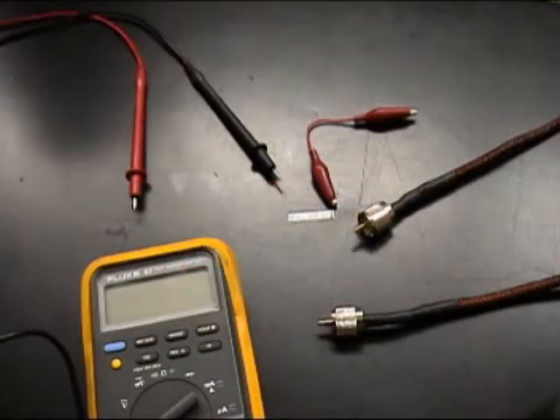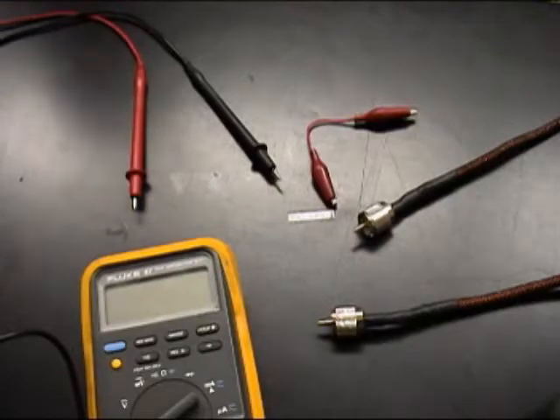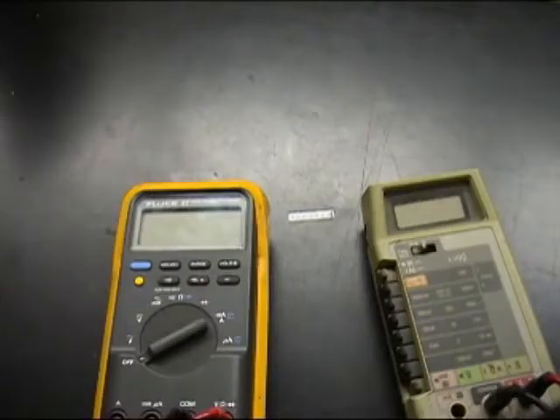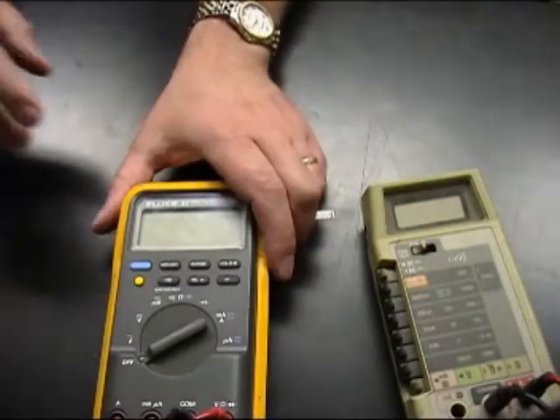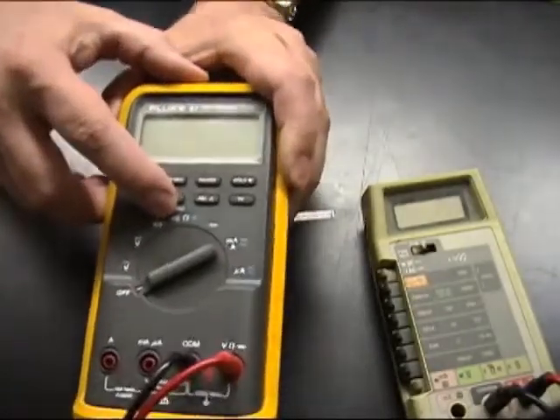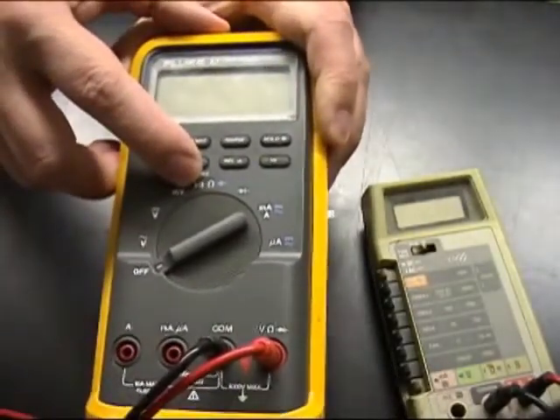PermAlert cable and connector testing procedures. The installation test should be run after the installation of each connector and the continuity test after the installation of both connectors on a section of cable. All of the testing will be done using a multimeter set to the resistance or ohms setting. The symbol for resistance on most multimeters is omega, or the upside down horseshoe symbol.